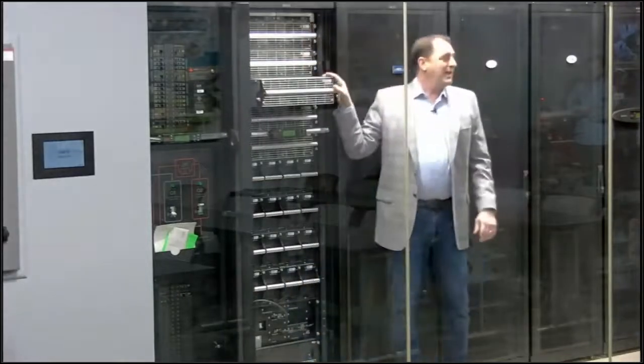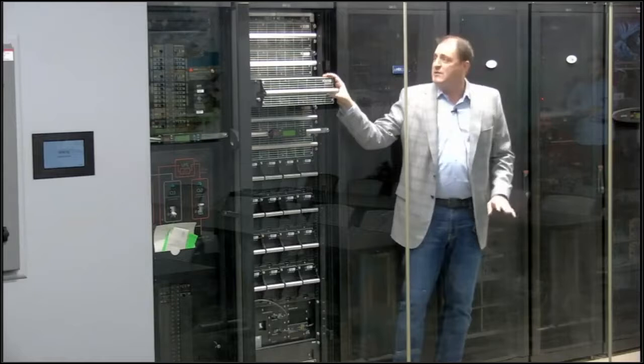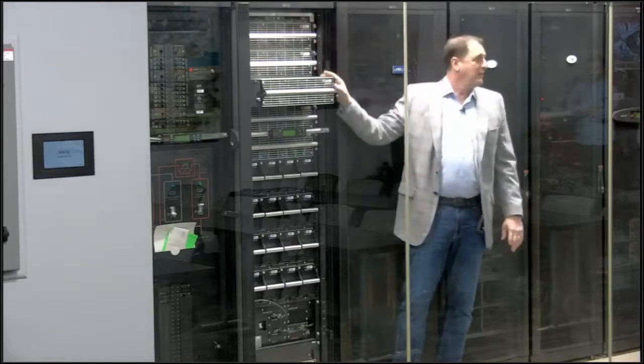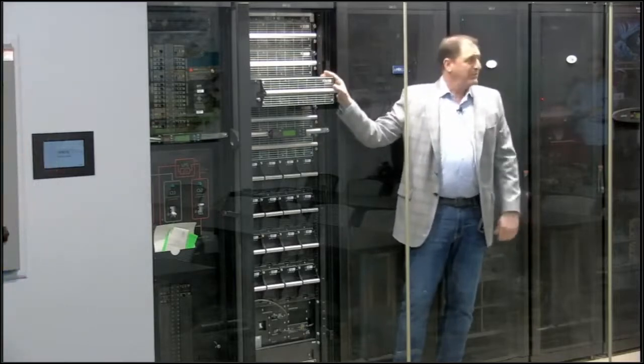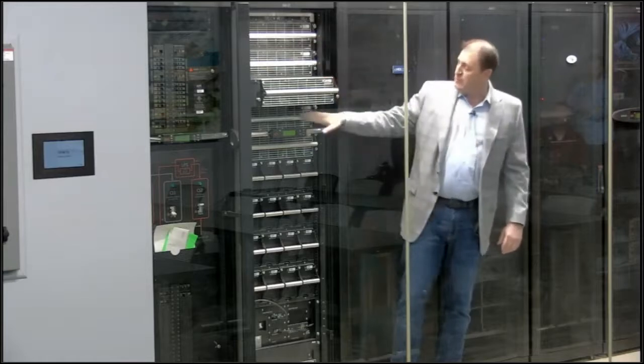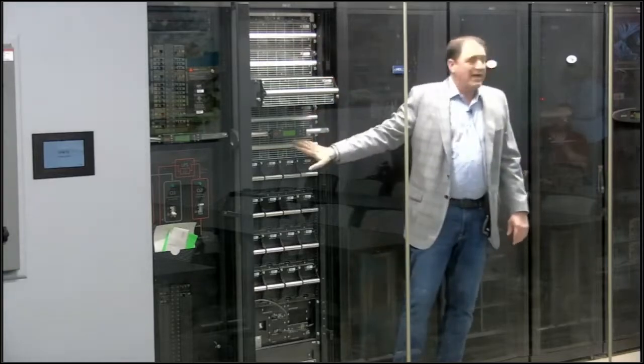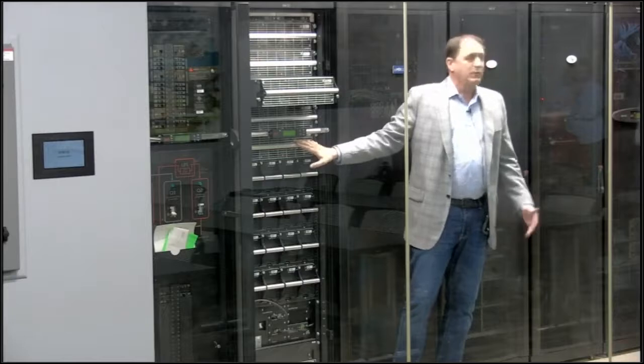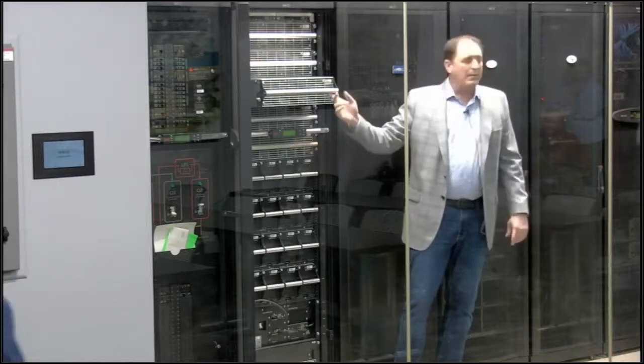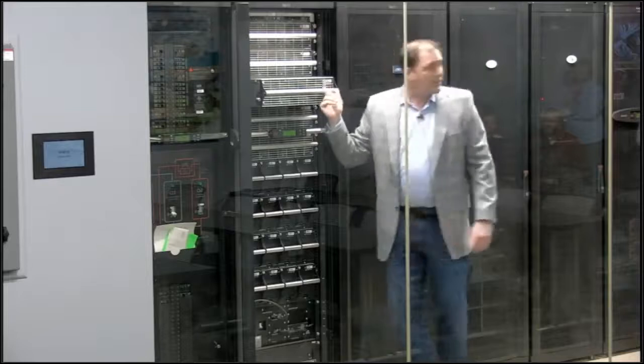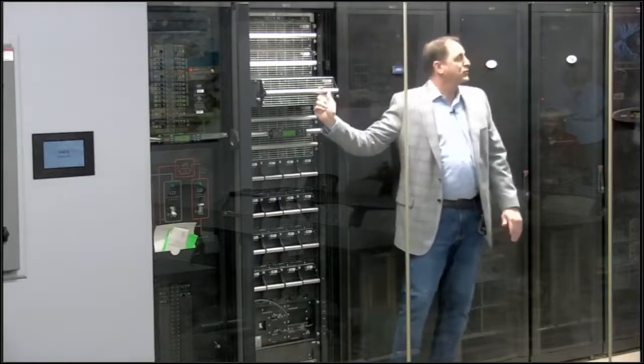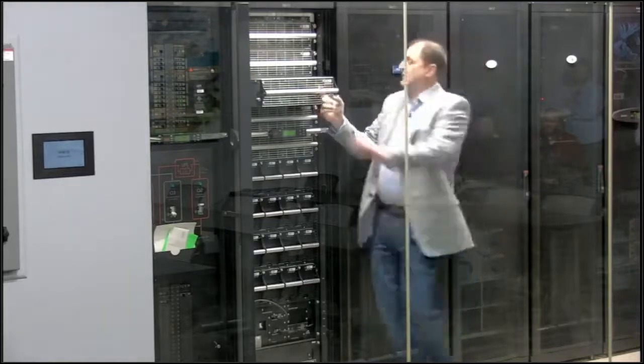I can simply take the module out of my UPS while the UPS is hot, while it is up and running. So I still have 1, 2, 3, 4 modules. I have a 40 kW UPS. So I'm going to slide this back in. Note that I'm doing this hot as electrical power is flowing to the machine.